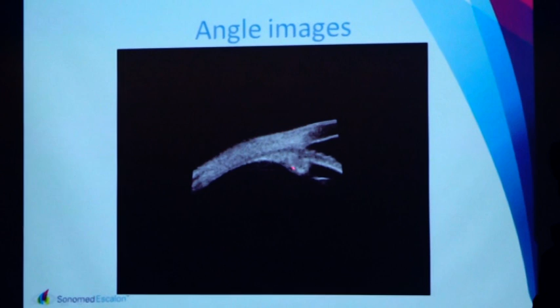Now as a final slide here, I'd like to show you the comparison between two frequencies of UBM, ultrasonic biomicroscope UBM. The standard frequency we provide with the machine is at 35 megahertz, but some doctors would prefer a higher frequency because they do angles. So we recommend when they do a lot of angle images that they use a 50 megahertz because shorter penetration of the ultrasound when it's a higher frequency. Okay, but you get a bit more resolution. As you can see here, the resolution difference.